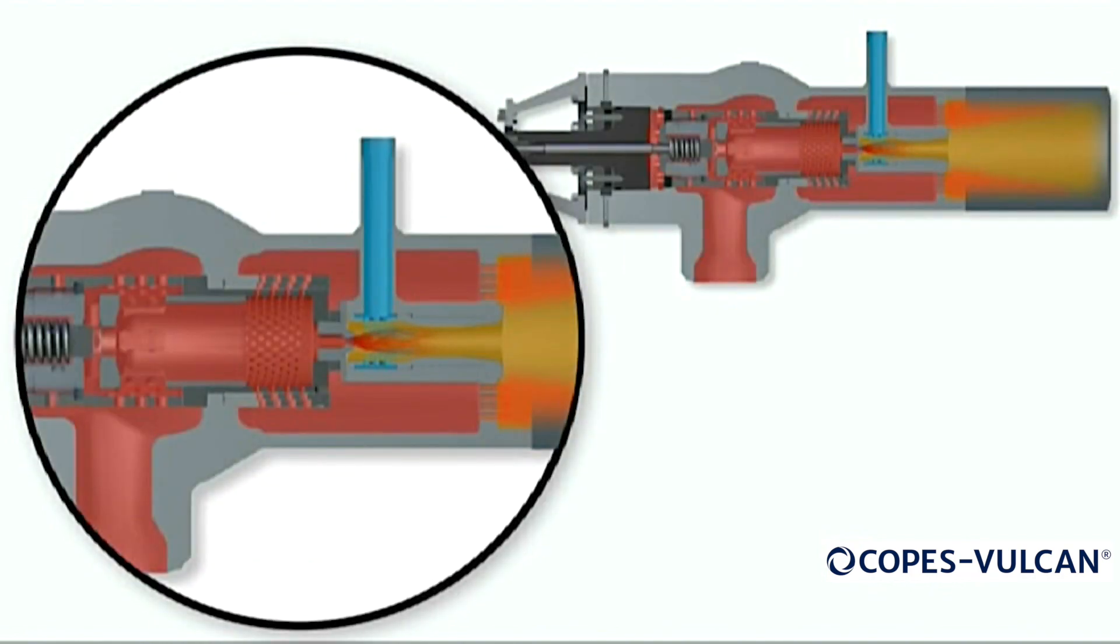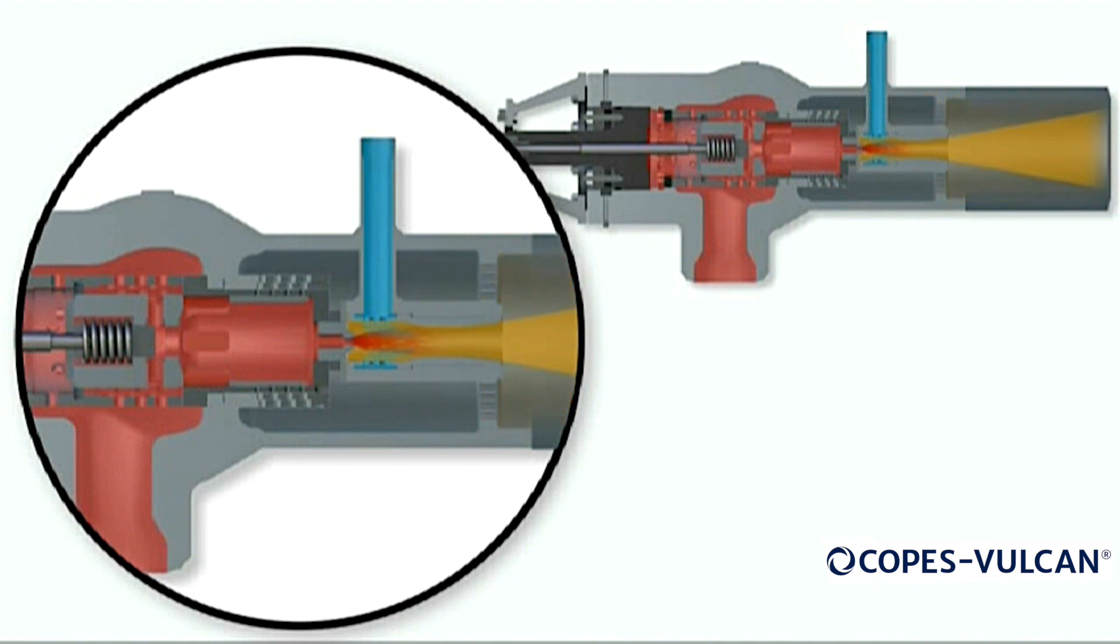When a closing signal is received, the main plug smoothly extends back into the cage, which proportionately decreases the steam flow rate. The main plug continues to close until the main seat is engaged. At this point, virtually all the steam flow has ceased. The actuator continues to extend until the pilot plug engages with its seat.